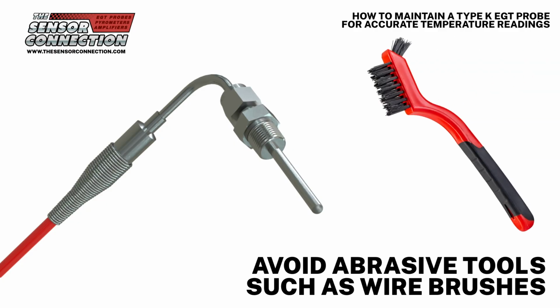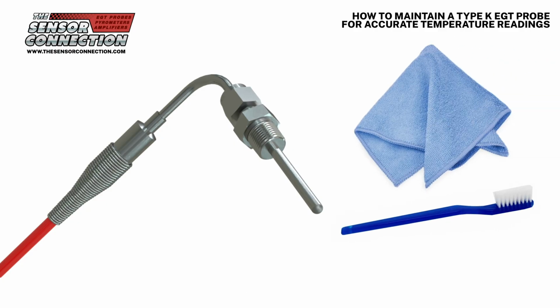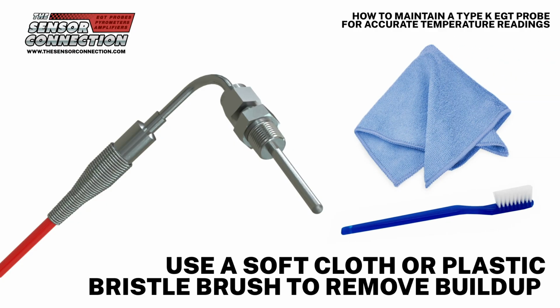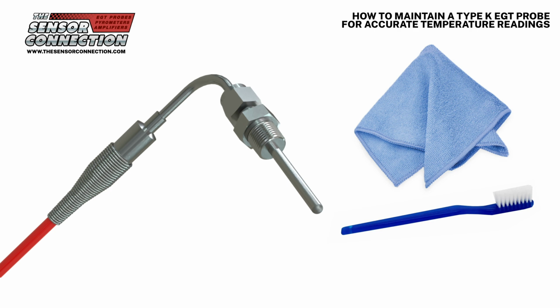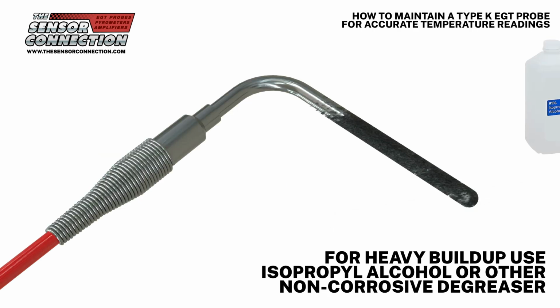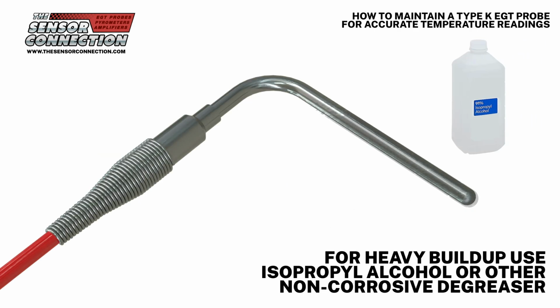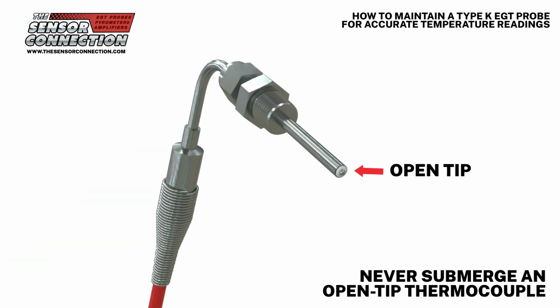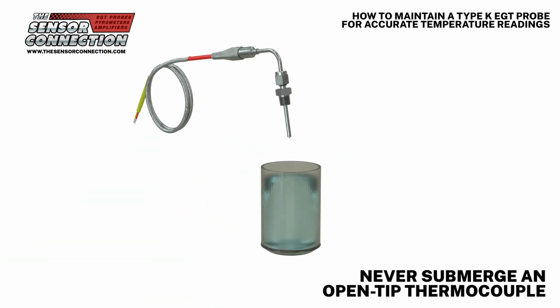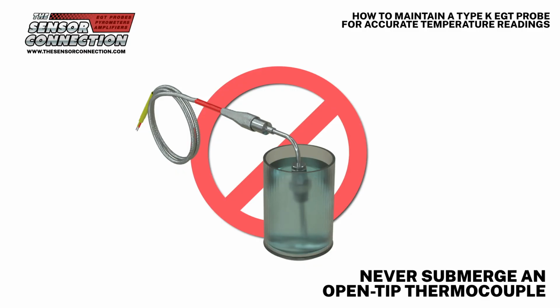If cleaning is needed, let the sensor cool completely before handling. Avoid abrasive tools like wire brushes. Instead, use a soft cloth or plastic bristle brush to gently remove carbon buildup. For heavier soot, you can use a mild solvent like isopropyl alcohol or a non-corrosive degreaser. Never submerge an open-tip thermocouple. Only closed-tip designs can be safely immersed in fluid.